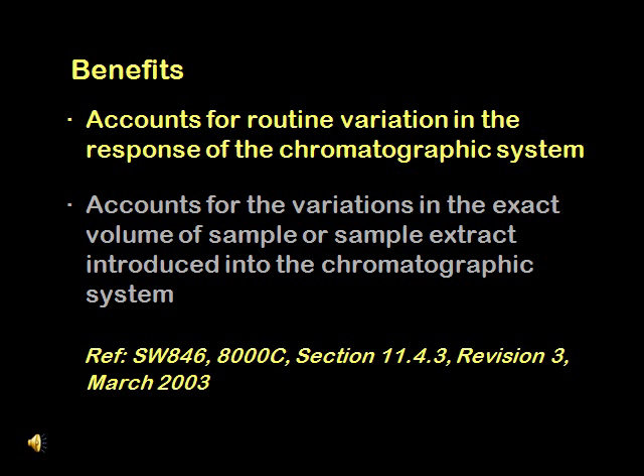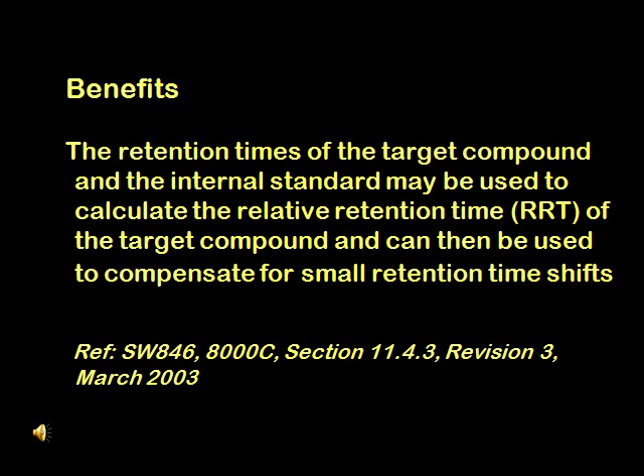The advantages of internal standard calibration are that it accounts for routine variation in the response of the chromatographic system in the case of organic analyses, and also accounts for routine variation in the exact volume of sample or sample extract introduced into the chromatographic system. Another advantage is that the retention times of the target compound and the internal standard may be used to calculate the relative retention time (RRT) of the target compound, which can then be used to compensate for small retention time shifts.